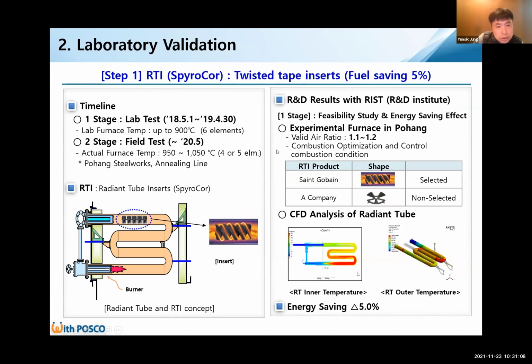Radiant tube inserts, so-called SpyroCor, are twisted tape inserts. They bring 5% fuel saving. Lab maximum furnace temperature was just set up to 900 Celsius degrees due to the limited lab circumstance. It has 6 elements, but the field test was performed at actual furnace temperature. I will explain this result later.